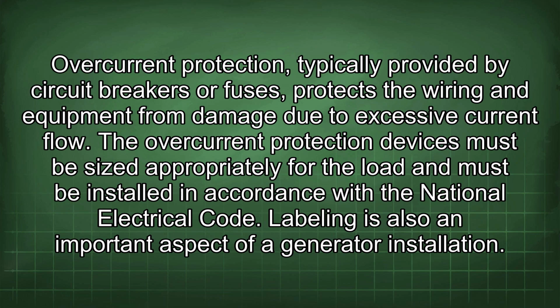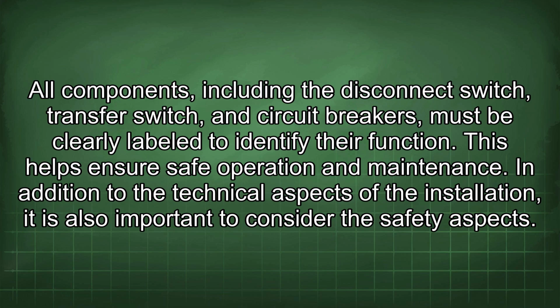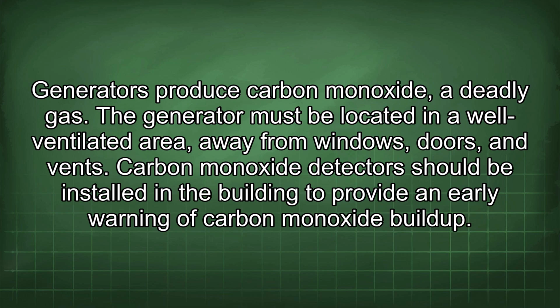National Electrical Code. Labeling is also an important aspect of a generator installation. All components, including the disconnect switch, transfer switch, and circuit breakers, must be clearly labeled to identify their function. This helps ensure safe operation and maintenance. In addition to the technical aspects of the installation, it is also important to consider the safety aspects. Generators produce carbon monoxide, a deadly gas. The generator must be located in a well-ventilated area, away from windows, doors, and vents. Carbon monoxide detectors should be installed in the building to provide an early warning of carbon monoxide buildup.